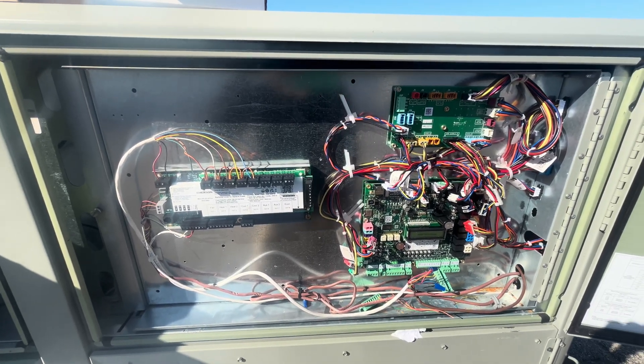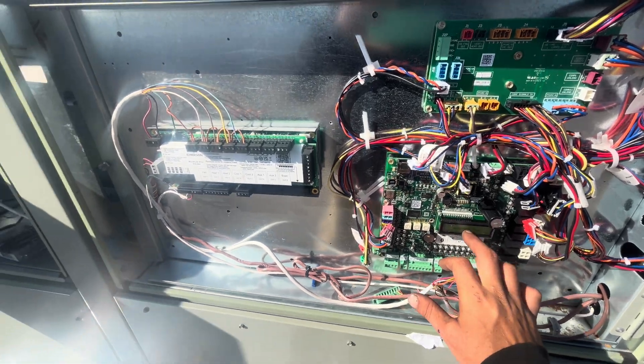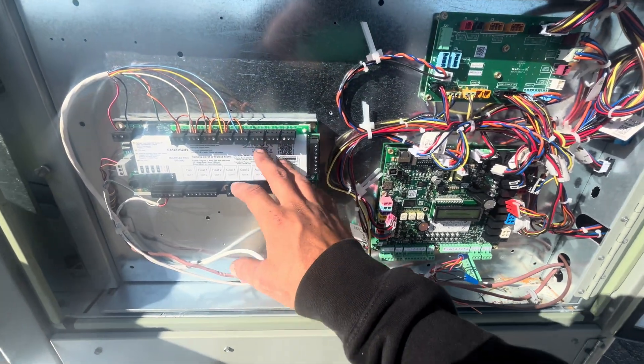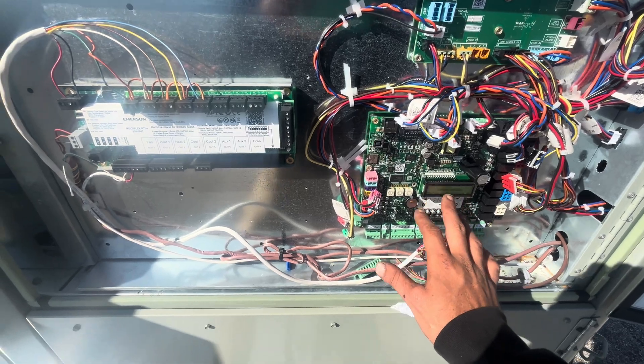We're back over at that Symbio 700 rooftop unit that went bad after they installed that Emerson relay board — essentially an energy management system. Something fried the board. Things just don't go bad like that, especially on a four-month-old unit. So what's going on here?